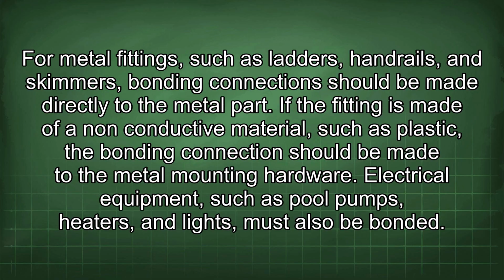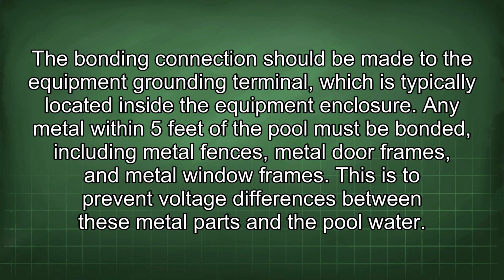If the fitting is made of a non-conductive material such as plastic, the bonding connection should be made to the metal mounting hardware. Electrical equipment such as pool pumps, heaters, and lights must also be bonded. The bonding connection should be made to the equipment grounding terminal, which is typically located inside the equipment enclosure. Any metal within 5 feet of the pool must be bonded, including metal fences, metal door frames, and metal window frames. This is to prevent voltage differences between these metal parts and the pool water.